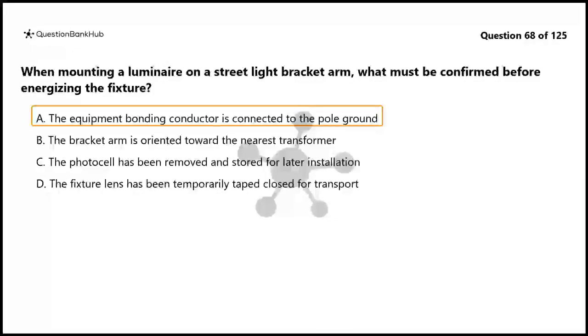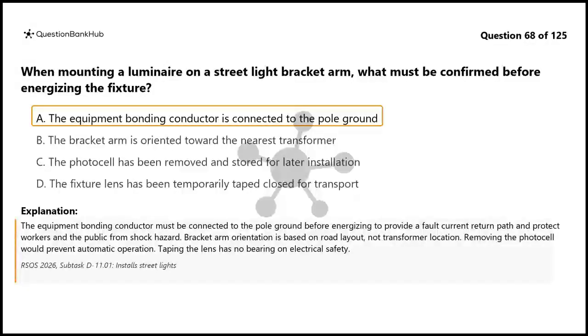The correct answer is A. The equipment bonding conductor must be connected to the pole ground before energizing to provide a fault current return path and protect workers and the public from shock hazard.